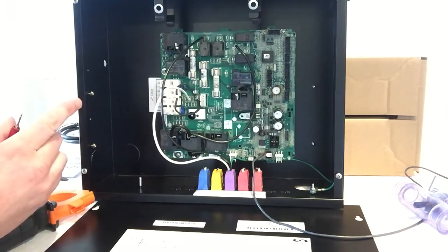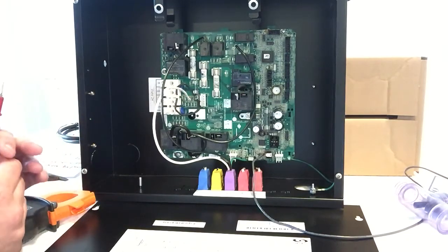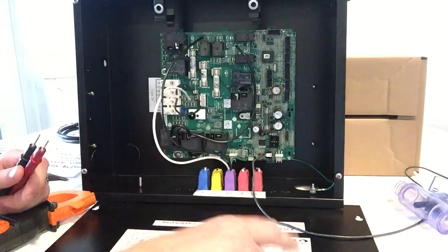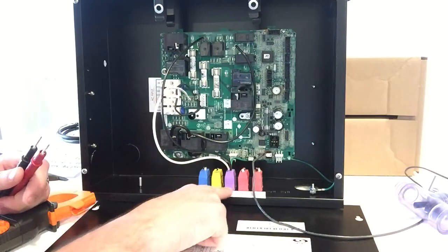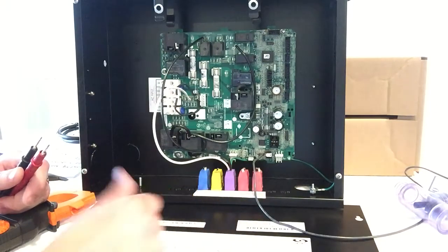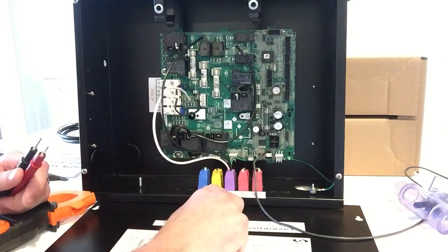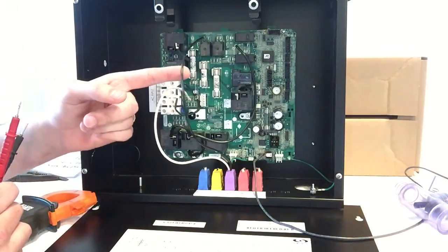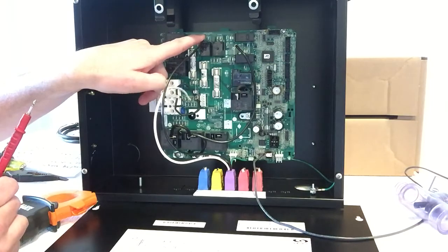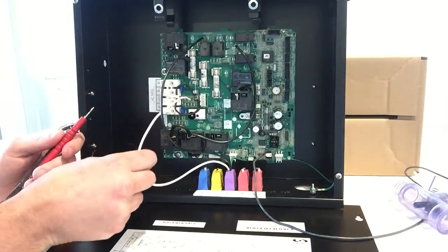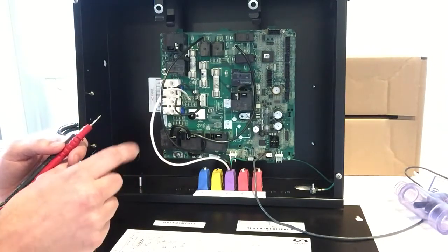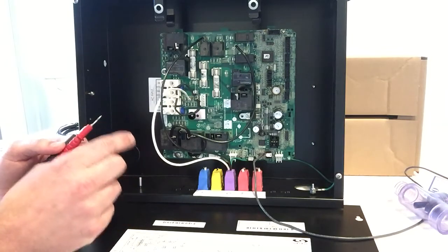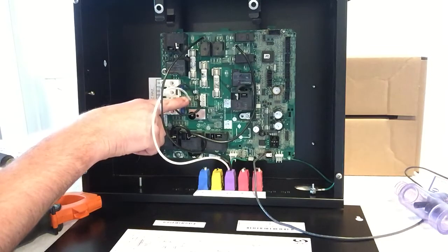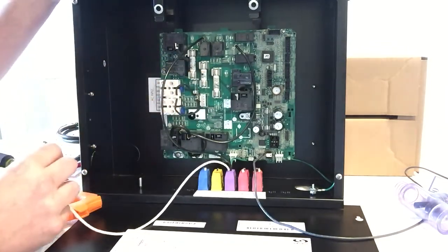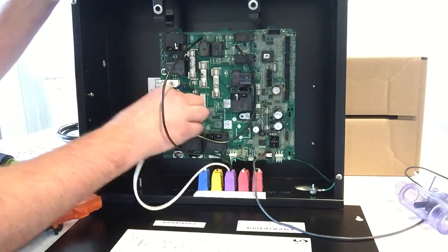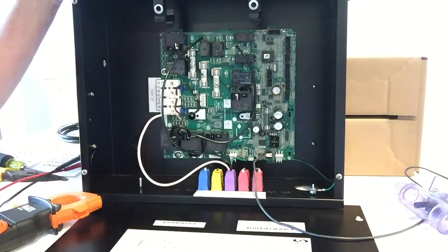Now, if the fuse is good, then we're going to have to check power to your circulation pump. So you find your pump, you follow where the cord plugs into the bottom of the box, and it plugs in right here. There's a label in here, but the lighting's off, so you can't see it on the screen right now. But find the one that says circ pump. Then you're going to follow the black wire. It's going to go up to a spot here that says P36. And the white wire, you're going to follow that. Depending on what pump you have, it will be in one of two locations. If you have a 120 volt circulation pump, it will be on P41. If you have a 250 volt pump, it will be on P54, which is down here. So just follow the two wires to where they hook up to the board.